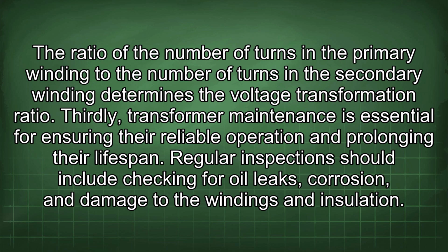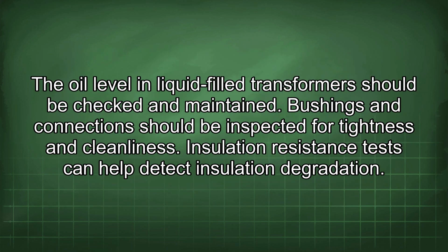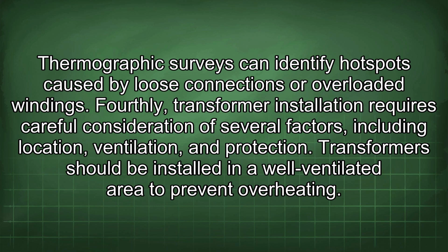Thirdly, transformer maintenance is essential for ensuring their reliable operation and prolonging their lifespan. Regular inspection should include checking for oil leaks, corrosion, and damage to the windings and insulation. The oil level in liquid-filled transformers should be checked and maintained. Bushings and connections should be inspected for tightness and cleanliness. Insulation resistance tests can help detect insulation degradation. Thermographic surveys can identify hotspots caused by loose connections or overloaded windings.